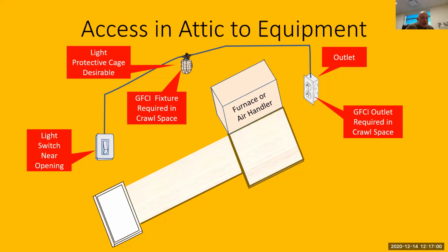On a construction site or industrial site today, the lights don't have to be GFCI, but because of deaths that have happened from broken bulbs, now that light and that receptacle in a crawl space has to be GFCI. Only in the crawl space, not in the attic.